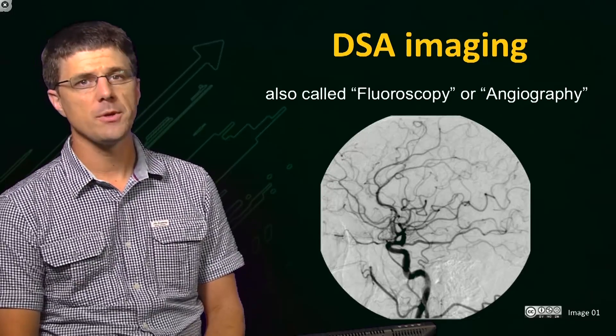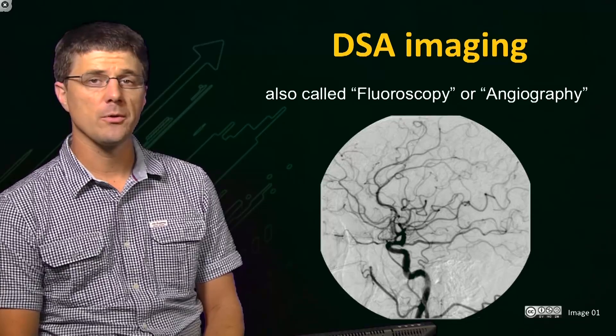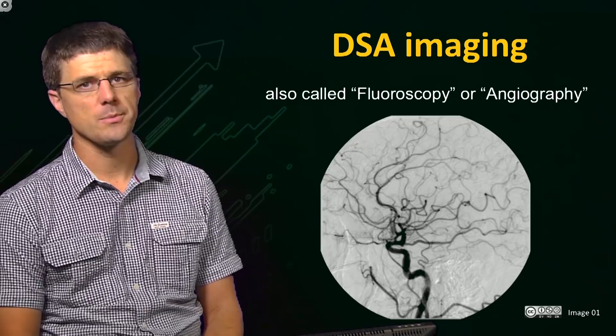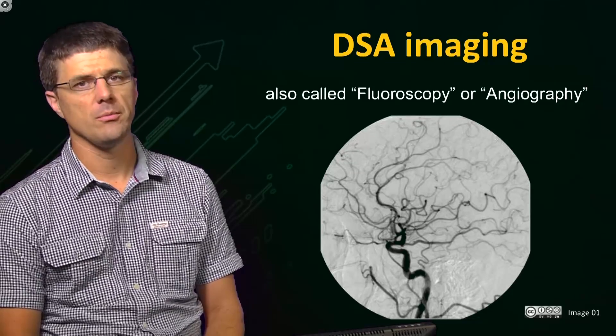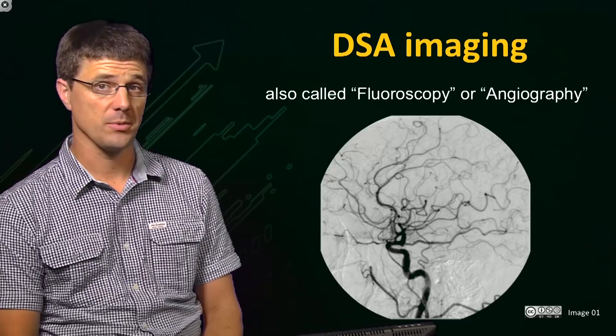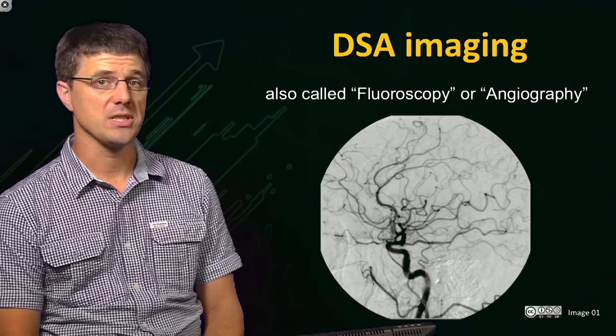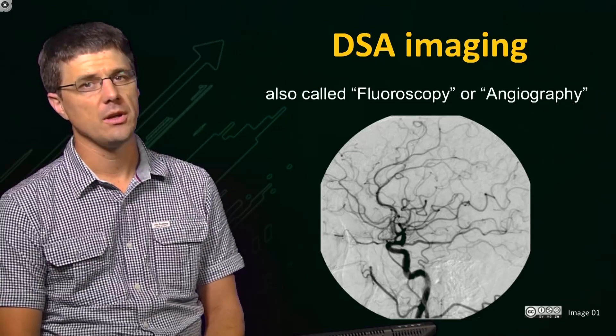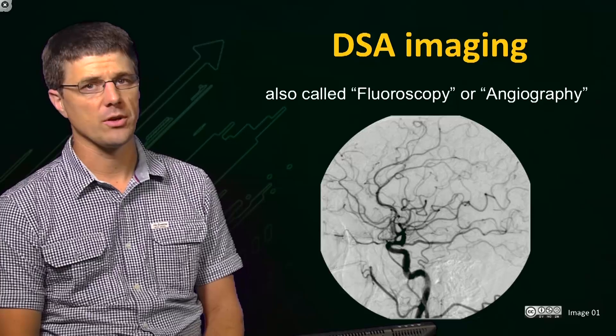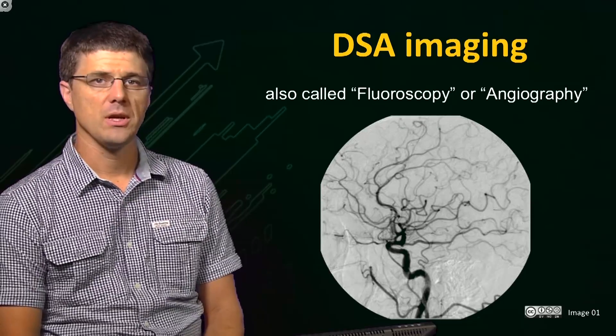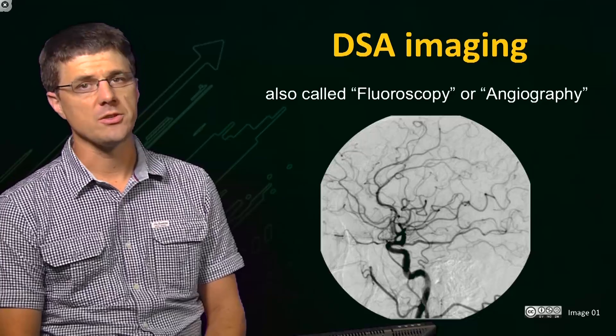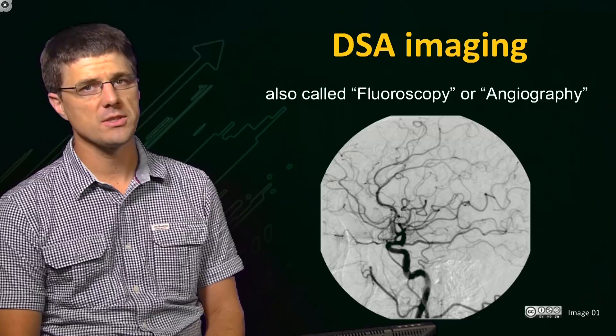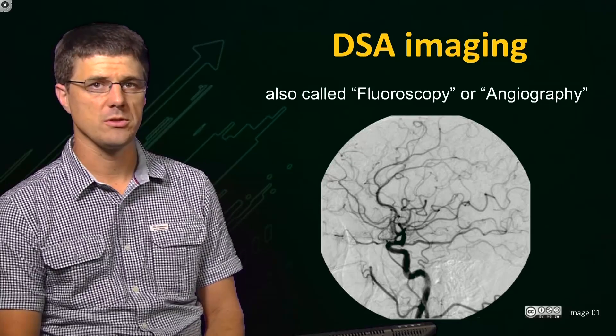In this image we see a typical DSA image. Like other reconstruction techniques, DSA imaging requires a number of computational steps that we will briefly describe. While these images look similar to fluoroscopy, they are generated by a different technique. In DSA, post-processing with a mask image is performed digitally rather than via a fluorescent screen. DSA stands for digital subtraction angiography, an X-ray imaging technique in which an initial pre-contrast image is subtracted from a post-contrast image.